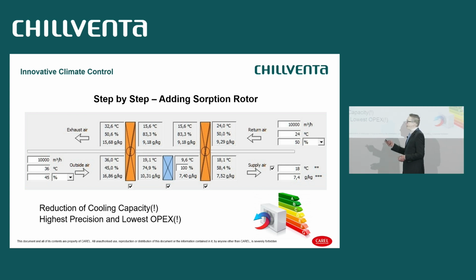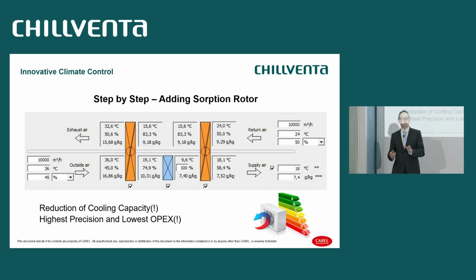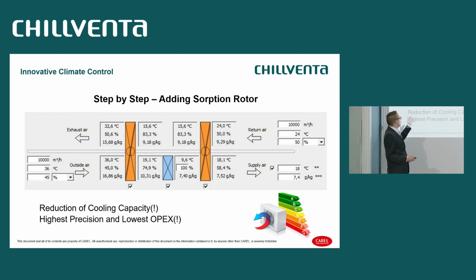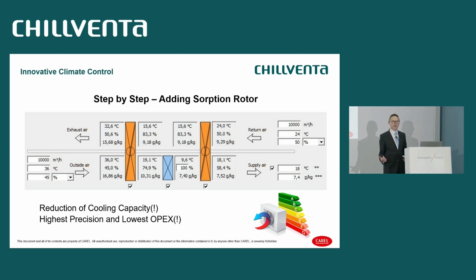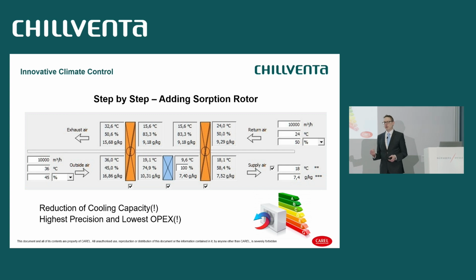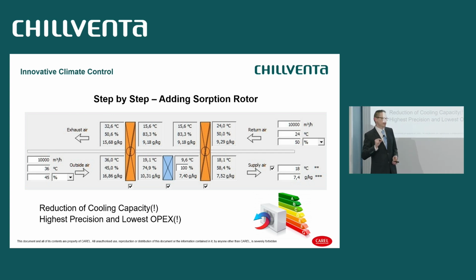So what happens here is by entering 36 degrees, just on the sorption wheel, a total energy wheel dealing with water, you get the 16.8 grams per kilo down to 10.3. So you have a system installed using, again, 180 watts, almost nothing in terms of auxiliary energy to make the wheel drive, to make it rotate. And you get out of the air just by nothing, just by putting it into the system. It's a no-brainer. You get down 6 grams. And these 6 grams per kilo, this is latent energy that the cooling coil does not need to supply, full stop.